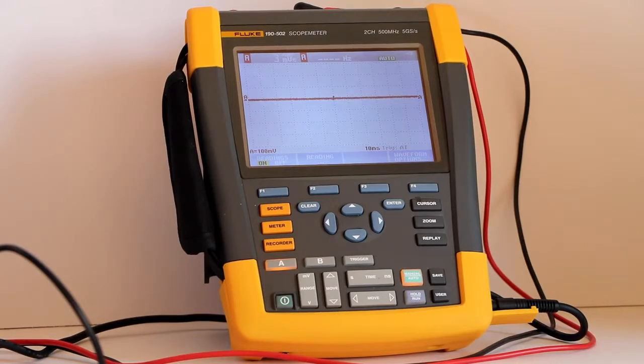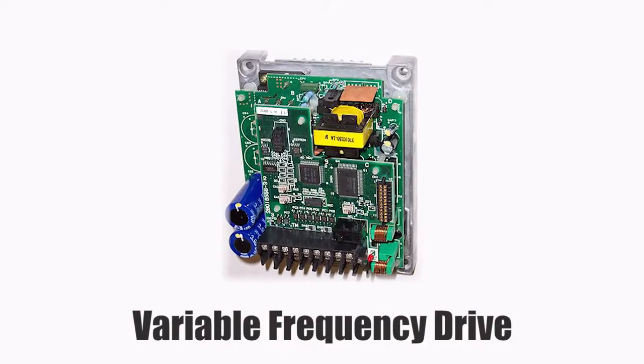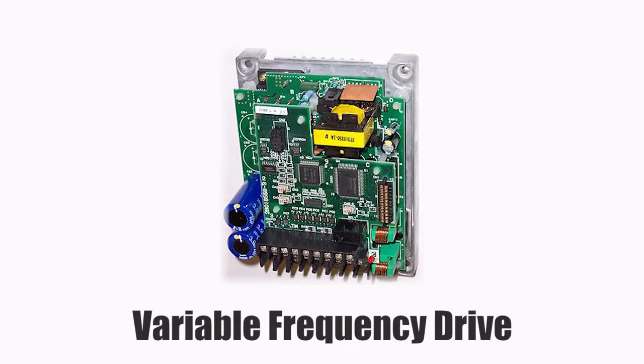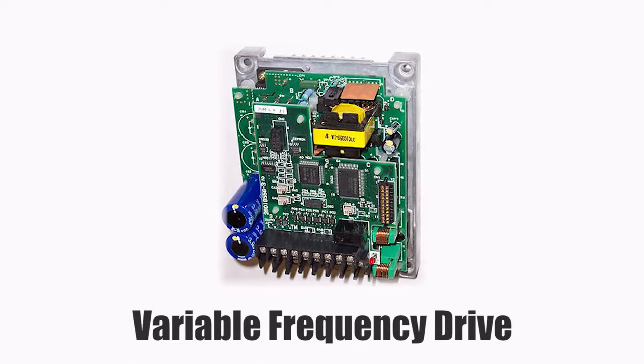Some devices, like a common incandescent light bulb, don't care whether they are powered by an impeccable wave. In fact, if the voltage is within operating range, they will not even distinguish between AC and DC. In contrast, sensitive electronic equipment thrives on a high-quality supply voltage and often exhibits one or more failure modes when there is a problem in this critical area. This is true in regard to an external power supply, and the same observation is applicable regarding certain internal voltages. An example is the variable frequency motor drive DC bus, where a stable, ripple-free direct current is needed.